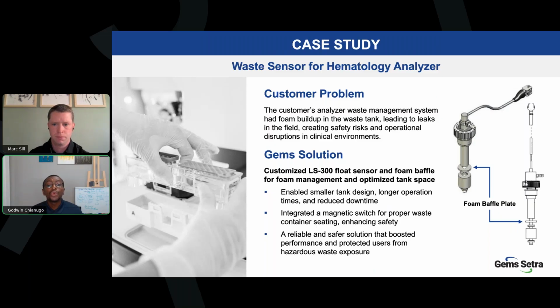To address this, we customized our LS300 high-level float sensor for their system. One of the key improvements was the addition of a foam baffle plate. This simple yet effective modification controlled foam buildup inside the waste tank, allowing the manufacturer to maximize the usable volume of the tank. The result was a more compact tank design, longer machine run times, and fewer service interruptions, all critical factors for busy clinical environments.